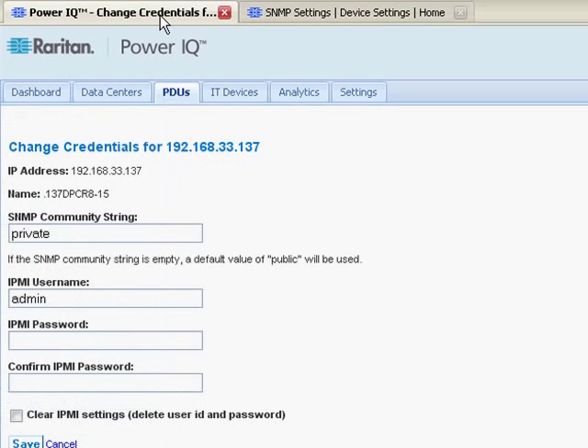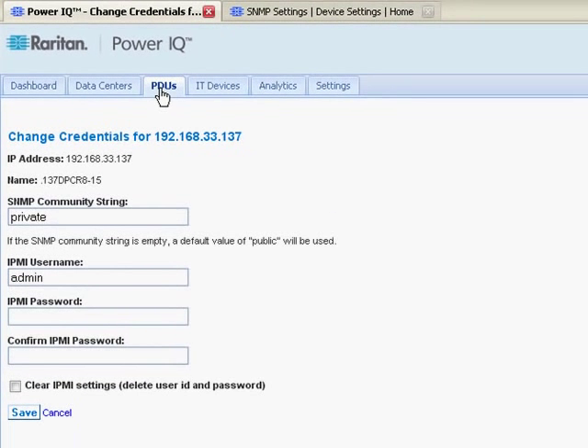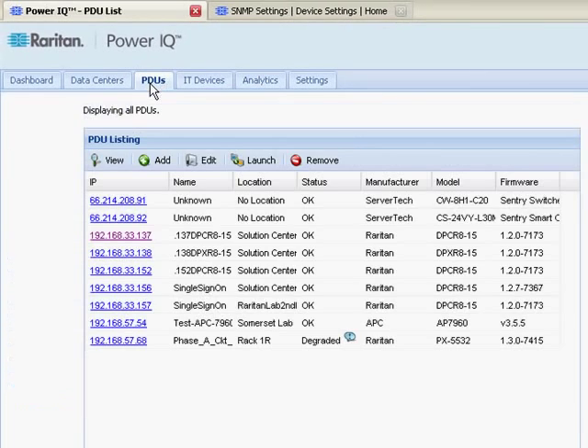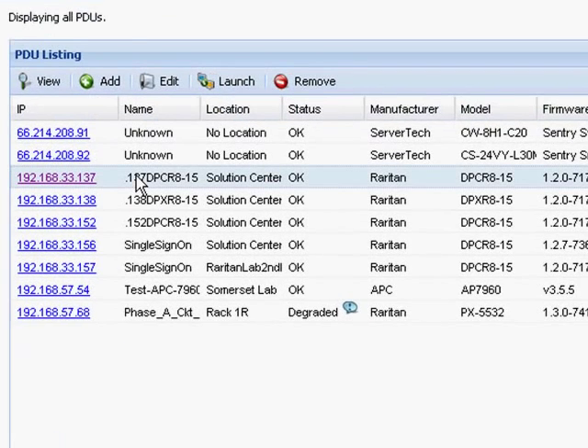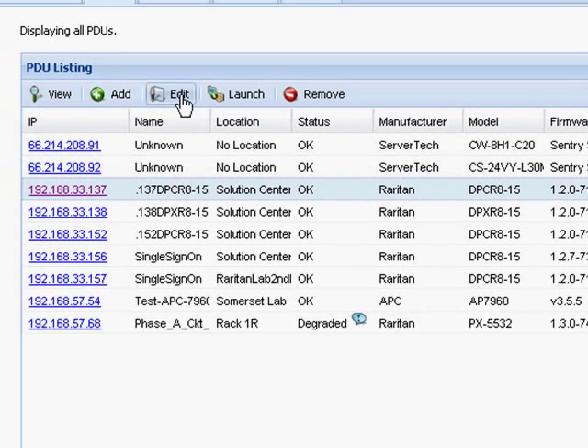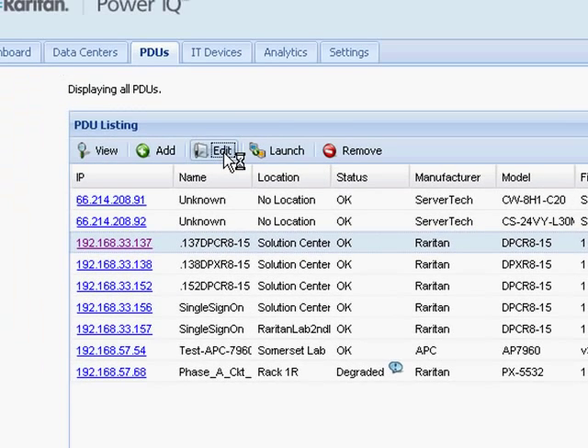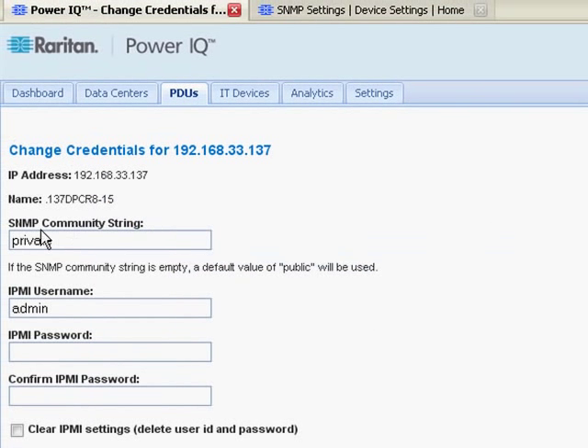So now I'd go to PowerIQ, so I switch tabs, I go to the PDU tab, I select the PDU that I want to collect the data from, highlight it, and I say edit. And this is where I enter the SNMP community string. The reason you want to enter the write community string, W-R-I-T-E, is that PowerIQ can both write to this PDU, so that you can name outlets, and also collect power data through the SNMP polling.